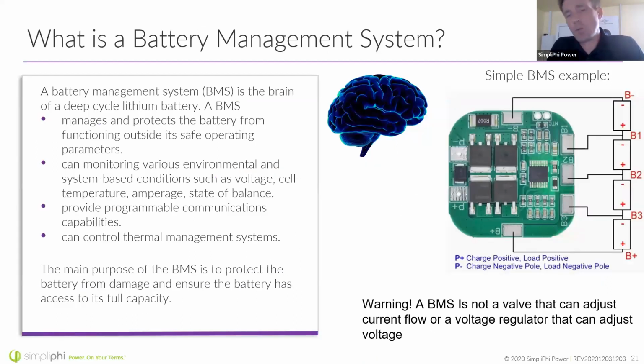Thank you. So let's jump into what the battery management system does. First, I want to address one thing that the battery management system cannot do. The battery management system is not a valve that can regulate current flow. If you have a charging device that's trying to charge the battery within the rated specifications of the breaker on the battery, and for AmpliPHI batteries, that's 100 amps, for SimpliPhi batteries, it's 100 amps, and for our Phi batteries, it's 80 amps, if you're within that range, the battery cannot regulate how fast current is flowing in. What it can do is protect itself by opening up a contactor, and I'll talk about that. But you need to make sure you're using appropriate charging equipment.